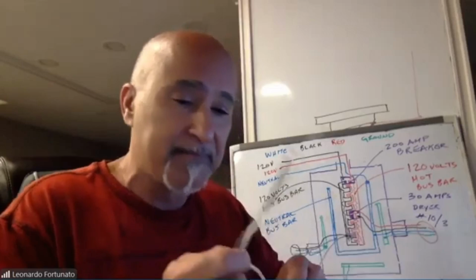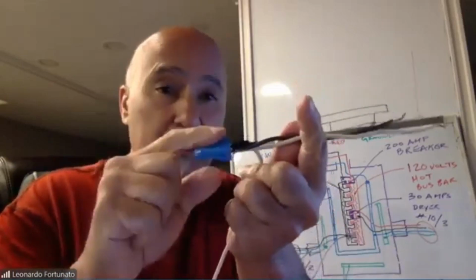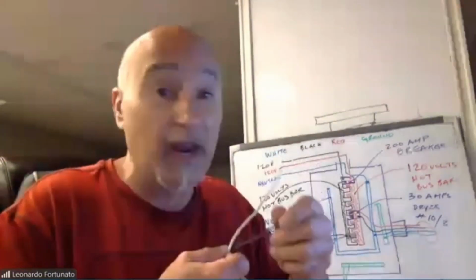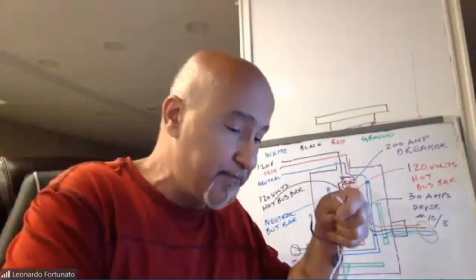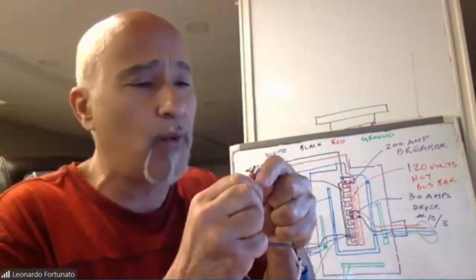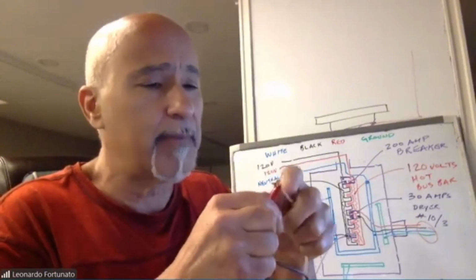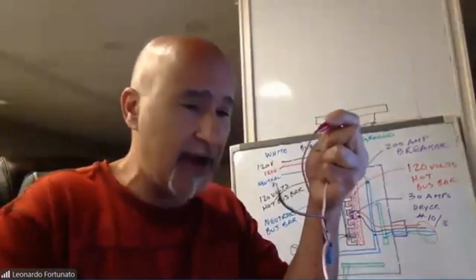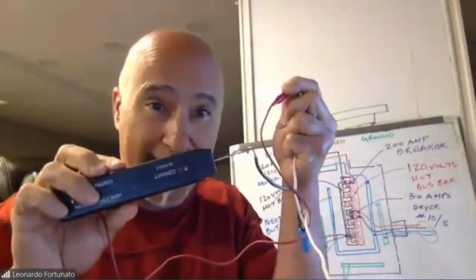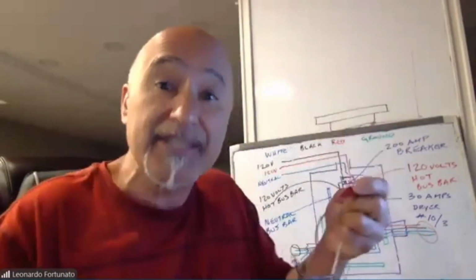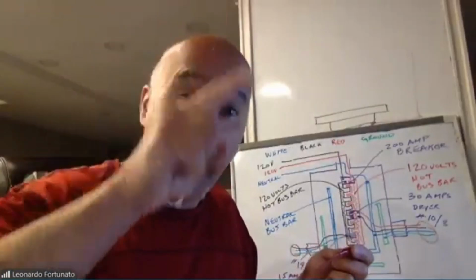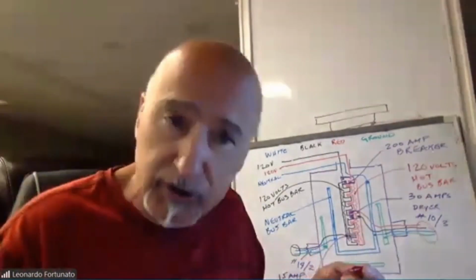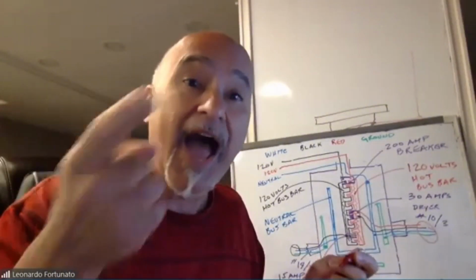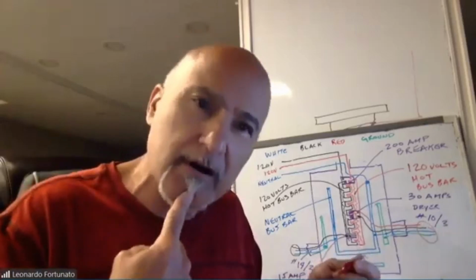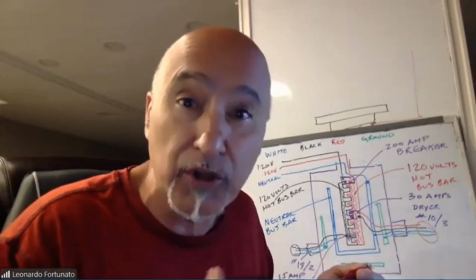Now I need to find out if the wire is broken somewhere, or if there's a connection that's not made properly. That's when we check for continuity. On one end we connect our wires together, and on the other end, where the light is or whatever we're checking, I put my connector on one wire and then touch the other side, without power. There's no battery in this one right now, so we can't check, but when you do this, if it lights up, everything is okay and the wires are connected end to end. You might still have faulty equipment, but that confirms continuity. If it doesn't light up, there's a break somewhere in the connection, and now we need to go find it.